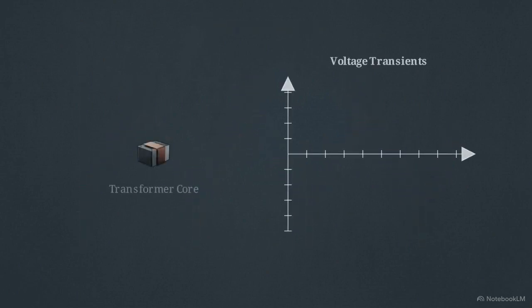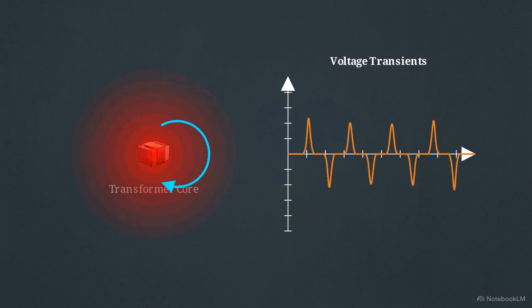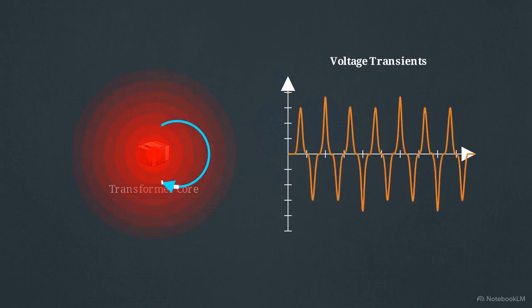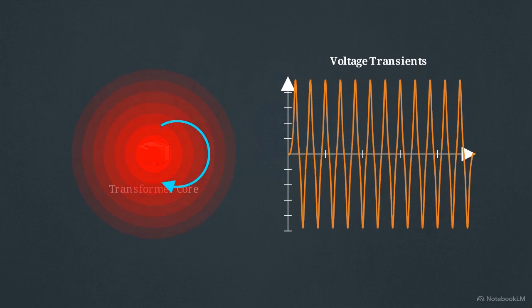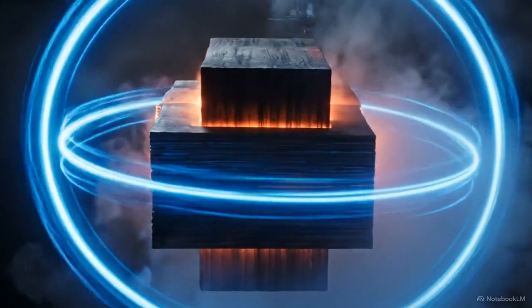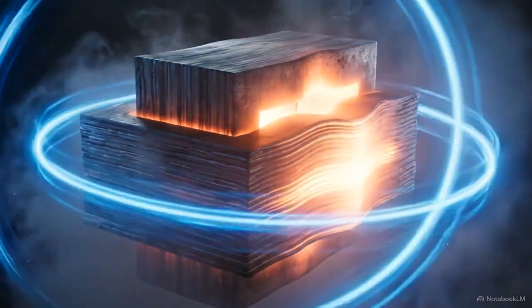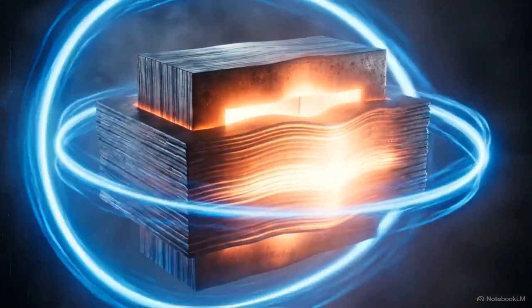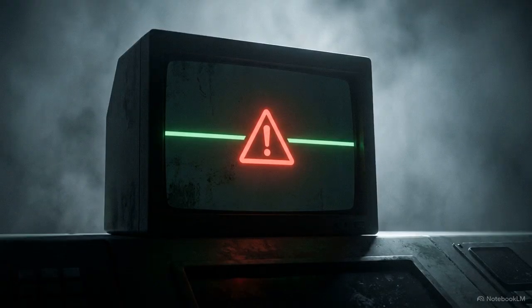When the transformer core saturates and its inductance drops, the flow of current surges. This sudden shift forces the voltage across the components to spike. That resulting high voltage immediately pushes the transformer core even deeper into saturation. This triggers another shift in inductance, which causes another voltage surge, speeding up the cycle into a runaway state. Because the saturated transformer continuously injects its own erratic excitation energy back into the circuit, it creates a self-sustaining feedback loop. Normal grid dampening mechanisms are essentially powerless to stop it.